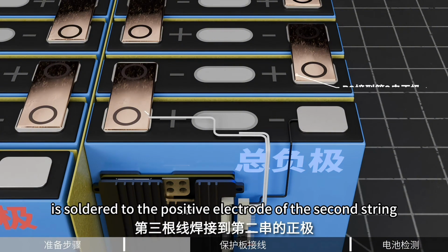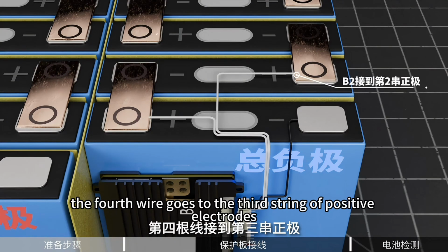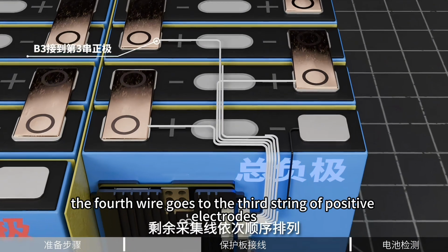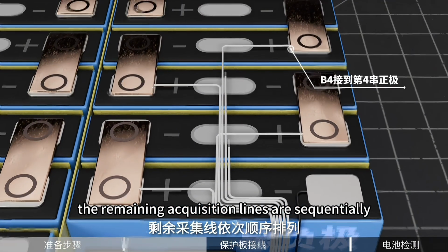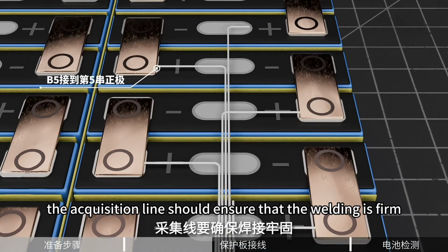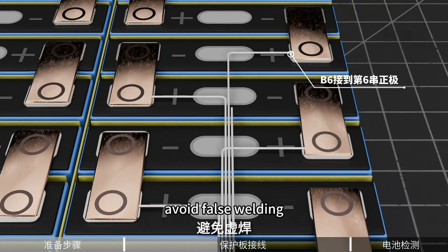The third wire is soldered to the positive electrode of the second string. The fourth wire goes to the positive electrode of the third string. The remaining acquisition lines are sequentially arranged to the positive electrode of each string. The acquisition line should ensure that the welding is firm. Avoid false welding.